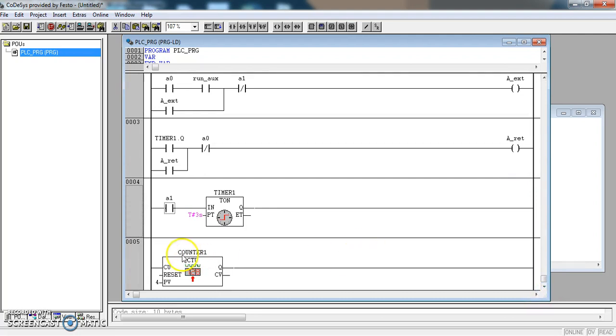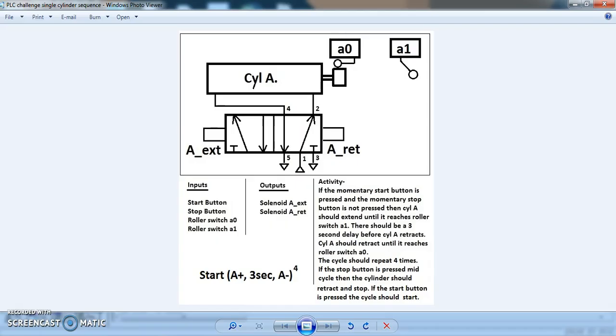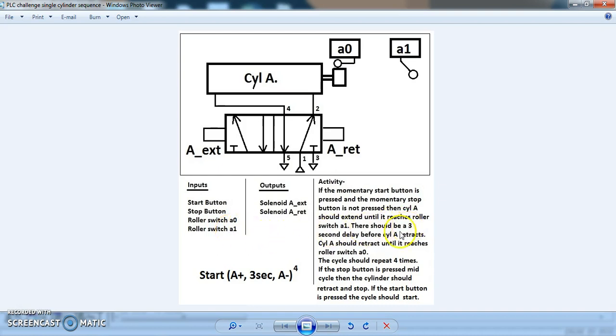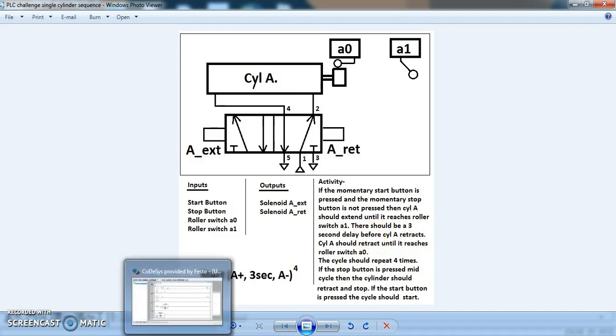Our counter also needs a trigger, and there are a number of things we could use. Going back to our system — I need this whole cycle to repeat 4 times. I can't use A0 because when the cycle starts it is already sitting on switch A0, so that would mean it would have a count of 1 before the cycle started. I can't use the start button because it only becomes active once in the entire cycle. I can't use the stop button because it may not become active at all. So the only one I can use is A1, or I could use the output from the timer. So I will use the output from the timer.